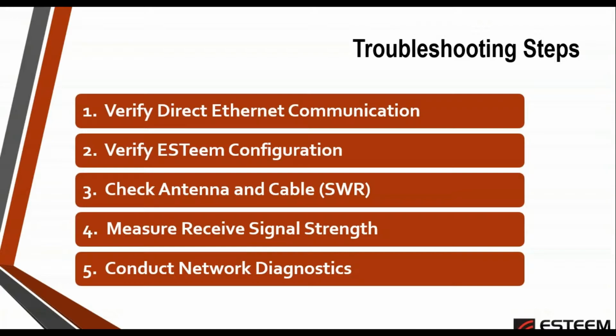Now, what happens in most control systems where these radios are applied is that all the communication tells you is that you've lost a remote site. It doesn't pinpoint exactly where the problem is, unless you've already integrated something like Modbus TCP, as we saw in the last section, where you can see the radios are communicating or check the signal strength. In most cases, all we know is the customer tells us we've lost this site. So what steps do we go through to make sure that happens?